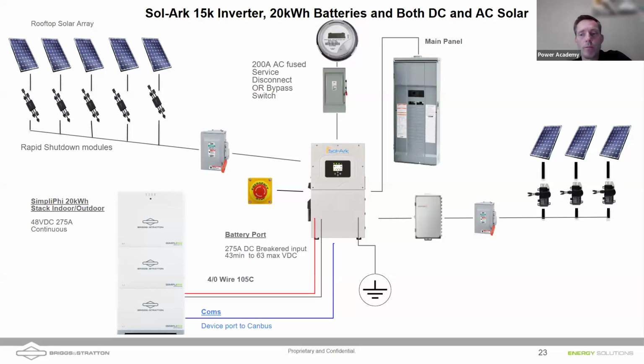And in fact, Sol-Ark recommends you can do up to 19.2 kilowatts of AC coupled solar, but Sol-Ark recommends that you actually have more DC coupled solar than AC. And so we can do both, bringing into, I think it's up to 35 kilowatts on that Sol-Ark 15K that's pictured. And of course, again, we want to make sure that with the AC coupled solar, the battery capacity is large enough to handle the power output of that solar array. So again, we still have a 20 kilowatt hour battery shown there.